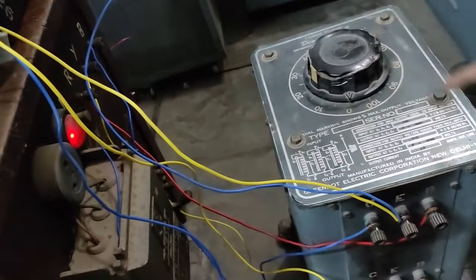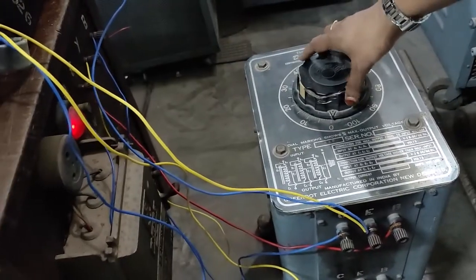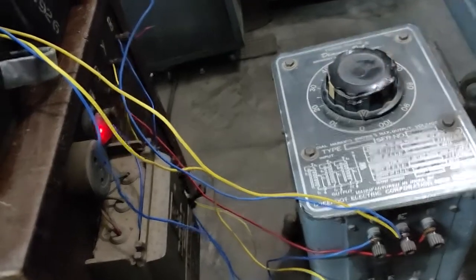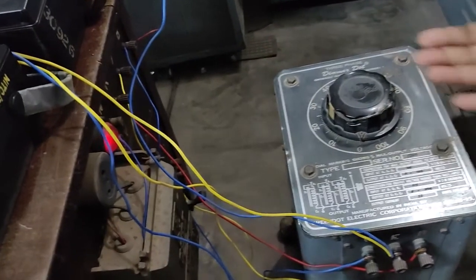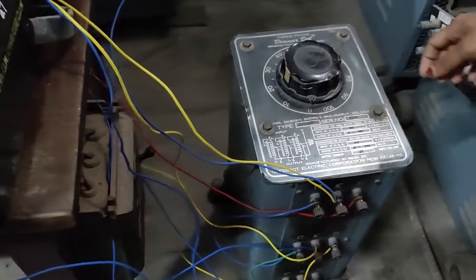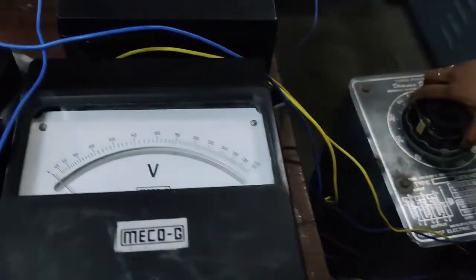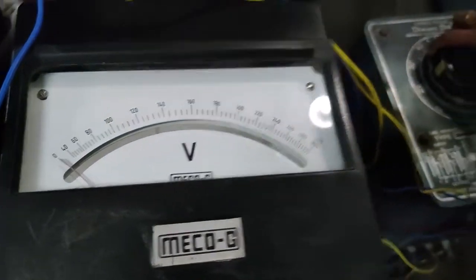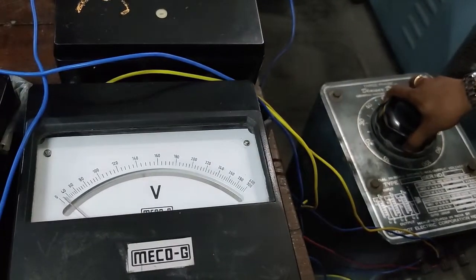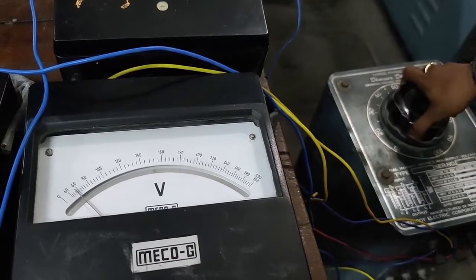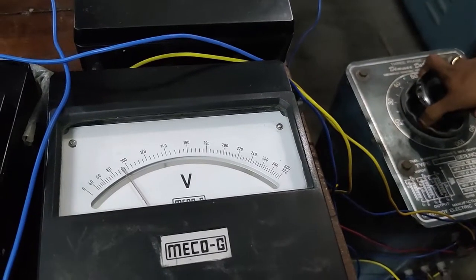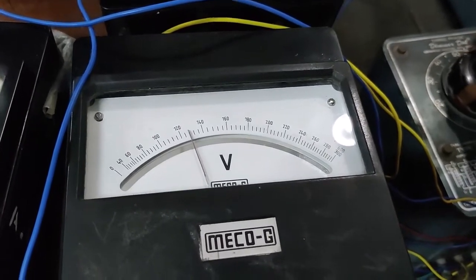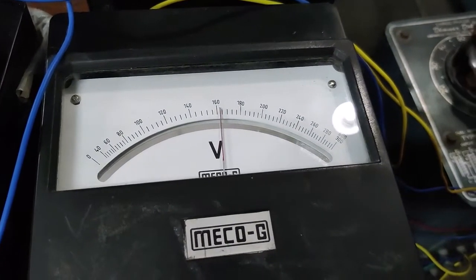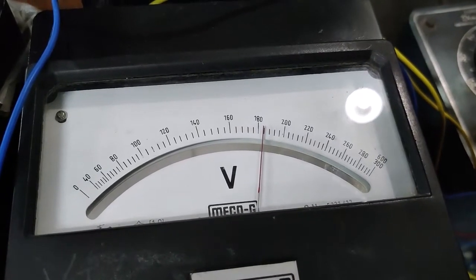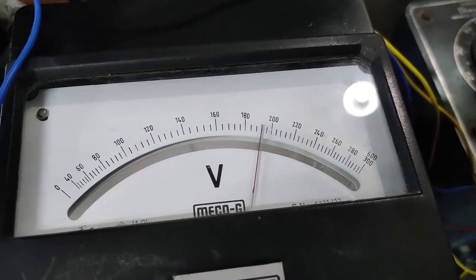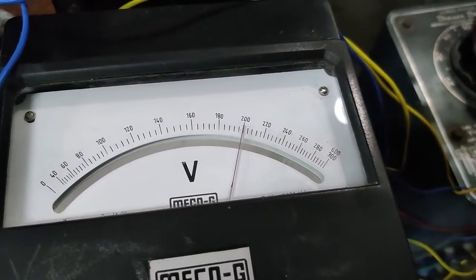Now all the loads are in safe position, and auto transformer is in minimum position, and let's switch on the supply side using switch S1. Then we are gradually increasing the rated voltage using the auto transformer. 400 voltage. So as the voltmeter has a multiplication factor of 2, now we have reached 400 volts.